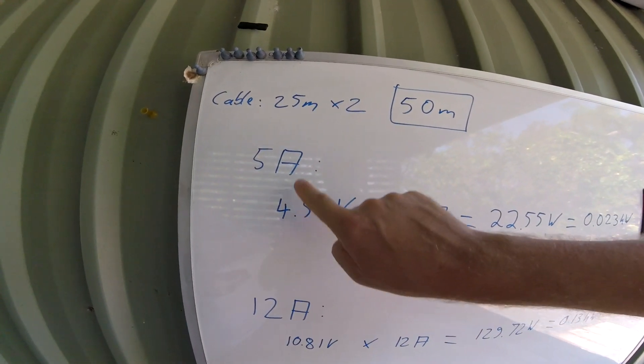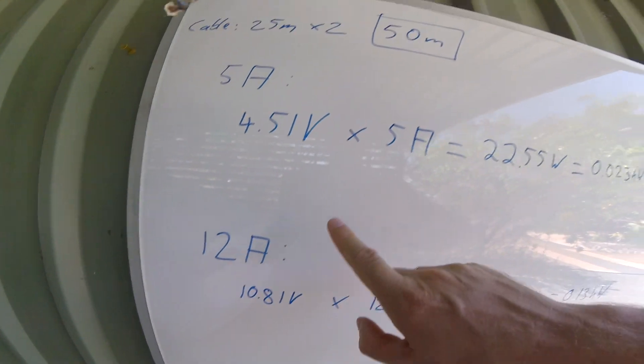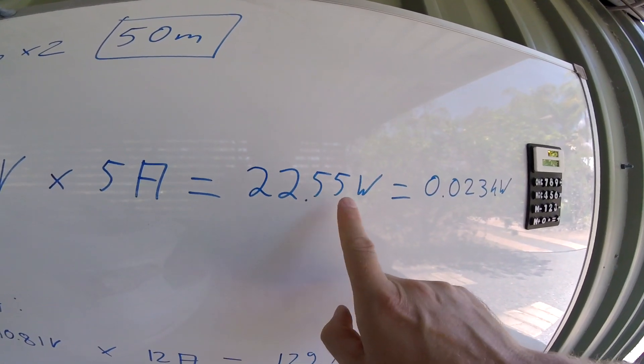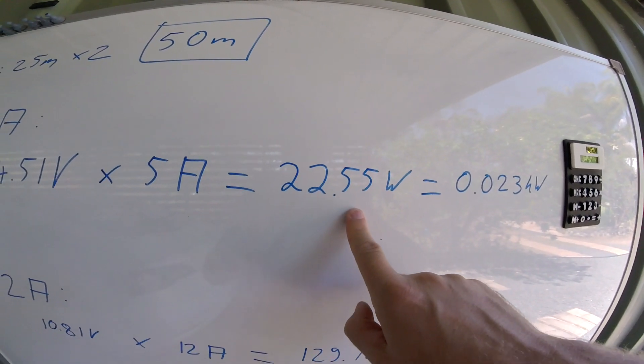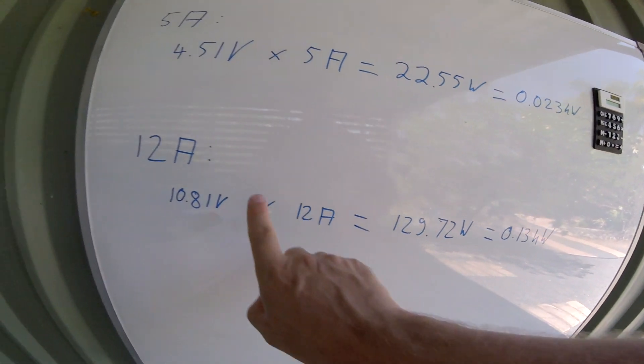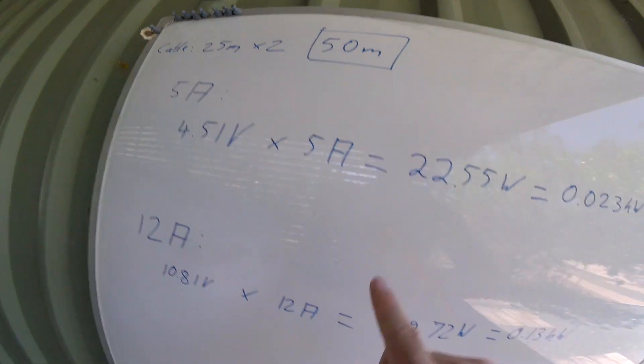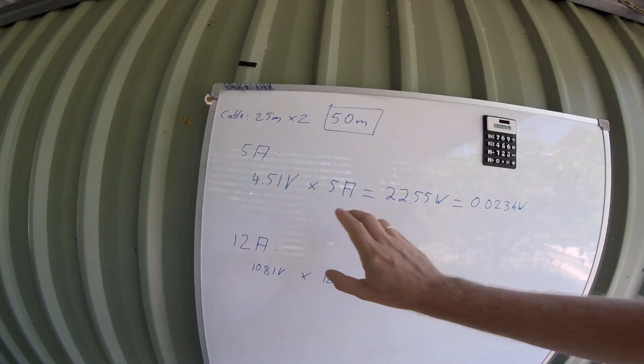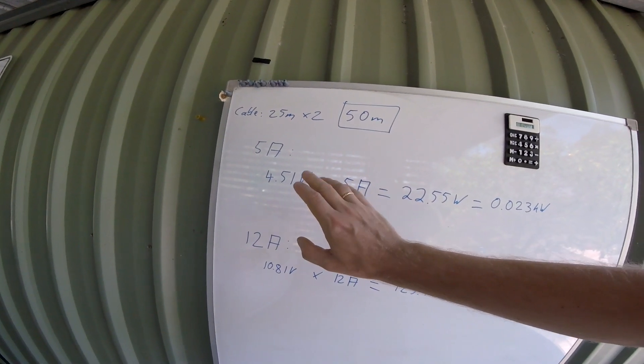We now have the voltage drop for 5 amp and 12 amp for the cable. I multiply this one by 5 amps and I get 22.5 watts will be lost on the cable. While on the 12 amp setting with the same cable, same length, we will have 130 watts. So alone from this, the 5 amp setting seems to be the far better setting to minimize voltage drop here.